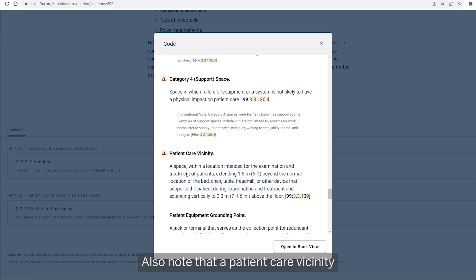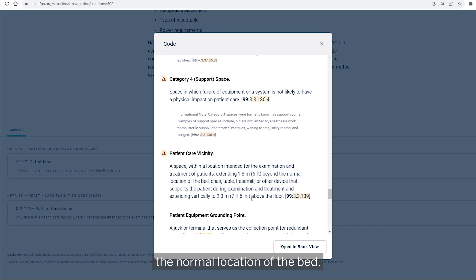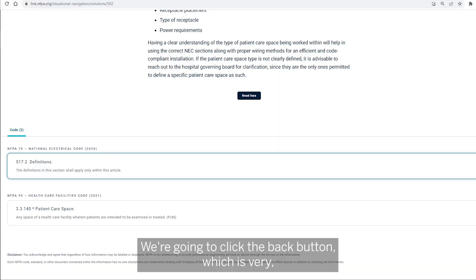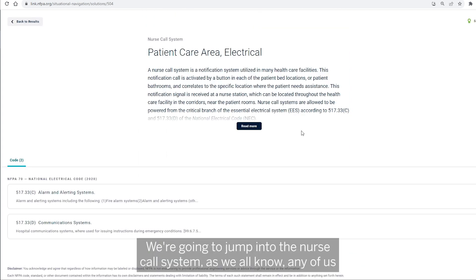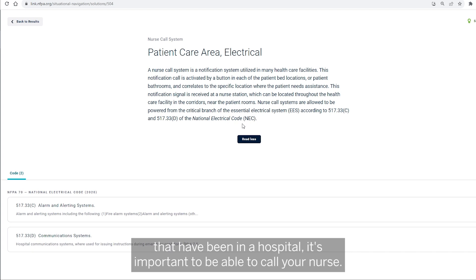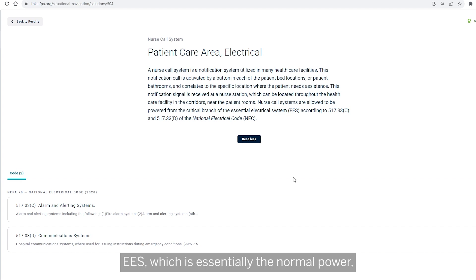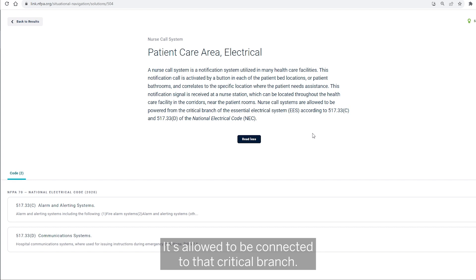Also note that a patient care vicinity is a space extending six feet beyond the normal location of the bed. We're going to click the back button — very important to note so that you don't lose your spot. Next we're going to jump into the nurse call system. Nurse call systems, because they're important, are allowed to be powered by the EES, which is essentially normal power backed up by an alternate source such as a generator or battery system, and are allowed to be connected to that critical branch.